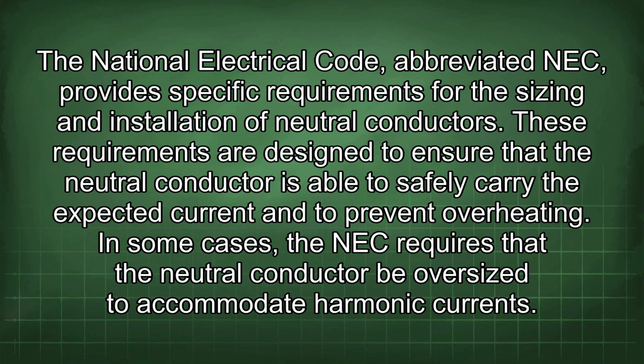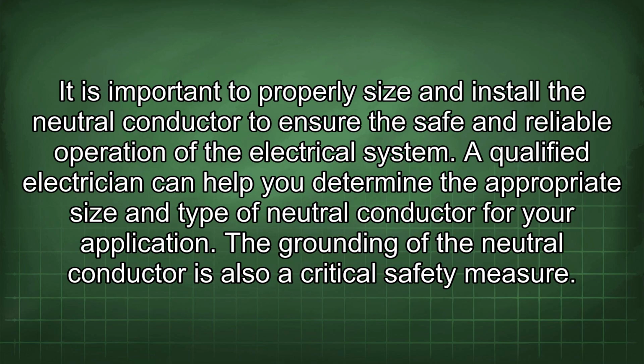The National Electrical Code, abbreviated NEC, provides specific requirements for the sizing and installation of neutral conductors. These requirements are designed to ensure that the neutral conductor is able to safely carry the expected current and to prevent overheating. In some cases, the NEC requires that the neutral conductor be oversized to accommodate harmonic currents. It is important to properly size and install the neutral conductor to ensure the safe and reliable operation of the electrical system. A qualified electrician can help you determine the appropriate size and type of neutral conductor for your application.